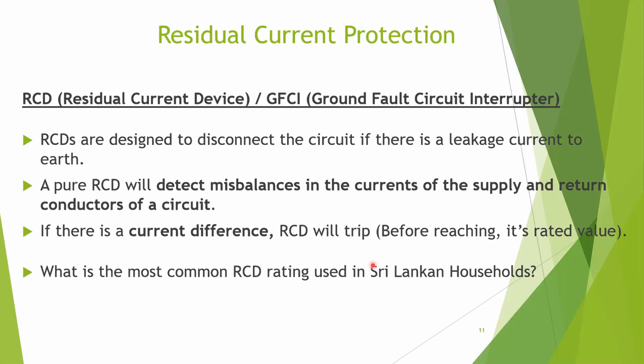I understand this lecture is a bit boring, but don't worry. Starting from the next lecture, you will be doing calculations and it will not be as boring as today's lecture. Okay. The most common RCD used in Sri Lanka is 30 milliamperes. After this lecture, go to your fuse panel and check the rating of your RCD. Usually it should be a 30 milliampere RCD. That is the rating recommended for households.